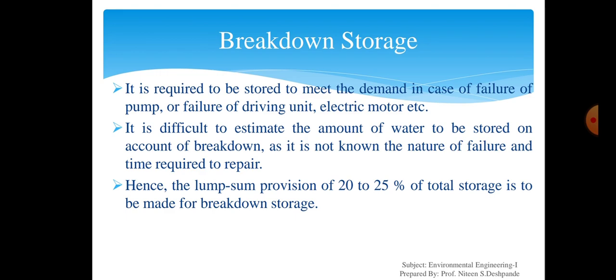It is difficult to estimate the amount of water to be stored on account of breakdown, because the nature of failure and the time required to repair are not known. So it is very difficult to predict the nature of the breakdown and how much time it will require to get it repaired. But it is customary to make a lump sum provision of 20 to 25% of the total storage.